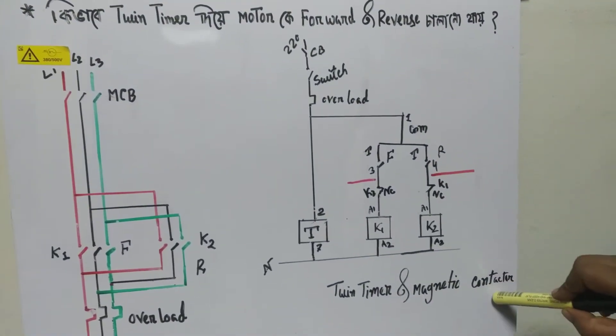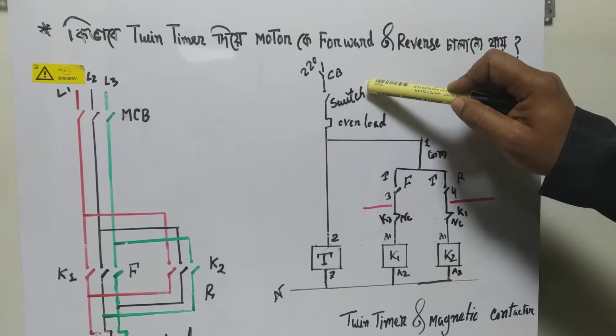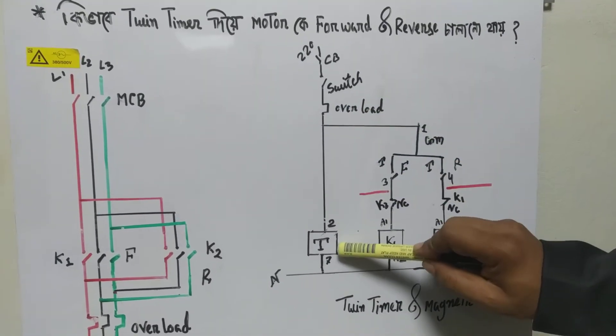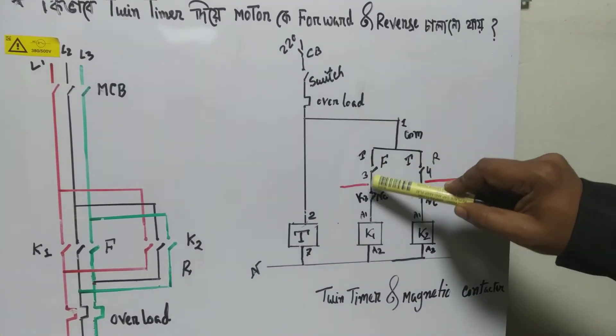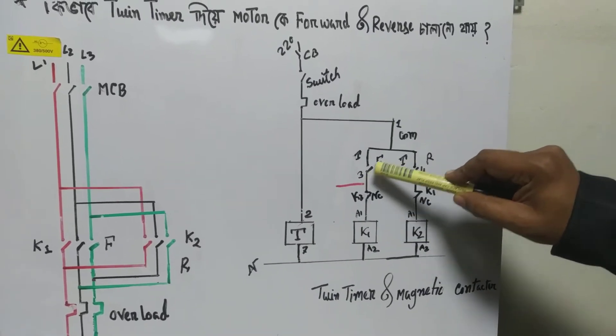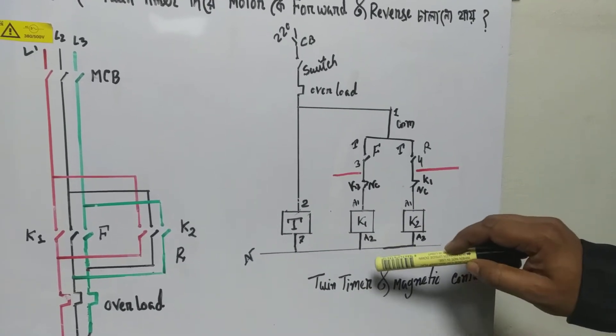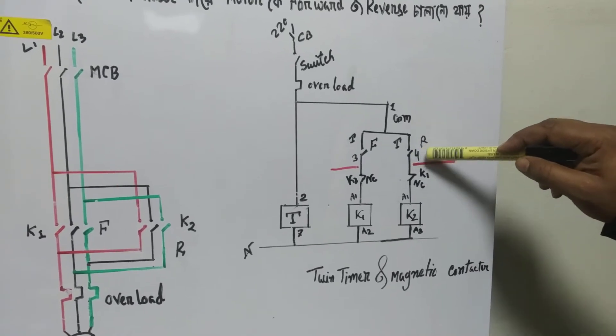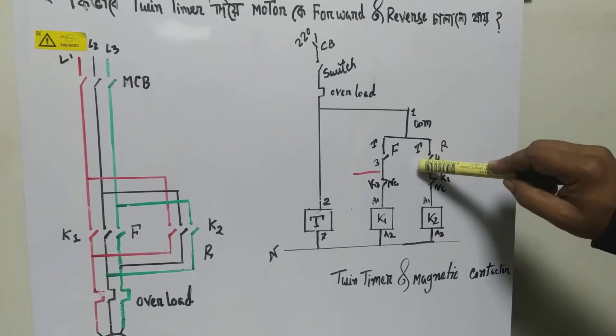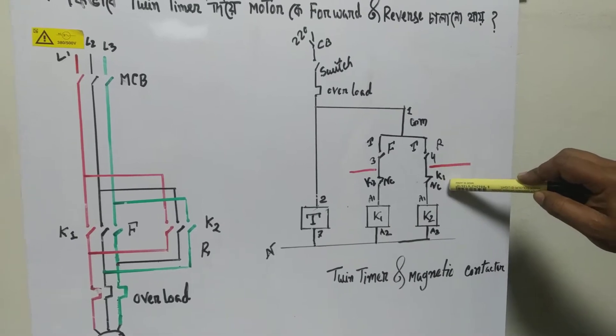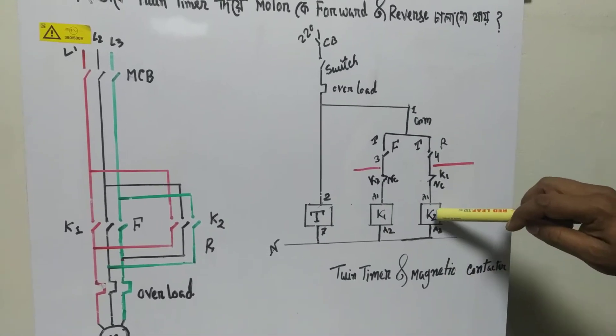From L1 and L2, the twin timer provides a forward signal which is connection number 3, and this will activate the forward magnetic contactor. The twin timer reverse is connection number 4. The magnetic contactors will have interlocking - if one is active, the other connector will be removed to prevent conflicts.